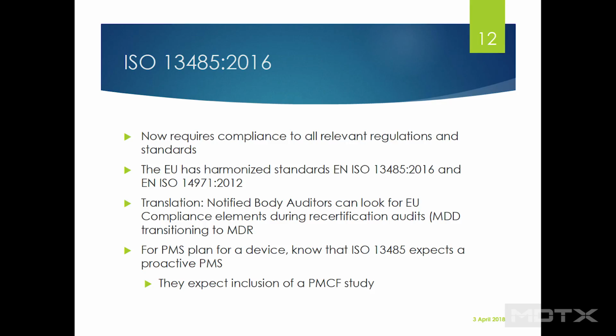And also, so here's kind of the translation, is that notified body auditors can look for EU compliance elements during a recertification audit. So even if you're getting a notified body audit, maybe certain products aren't in Europe yet, or you haven't even gone to the European market yet, but you're going, and you've stated that you're going, they have the right to look for the required elements for that market when you get a 13485 audit. Okay.